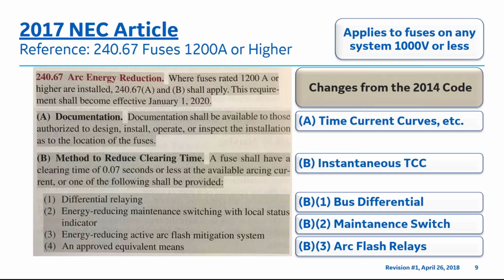B4, approved equivalent. The State Electrical Inspector, or AHJ, authority having jurisdiction in your local area, may approve of a different method to reduce arc energy for fuses 1200 amps or higher. These application examples provided in this EasyPower session will revolve around the existing IEEE 1584-2002 standard for arc flash calculations. IEEE presently has a 1584 working group updating the arc flash equations, which you can receive updated information from the IEEE website.